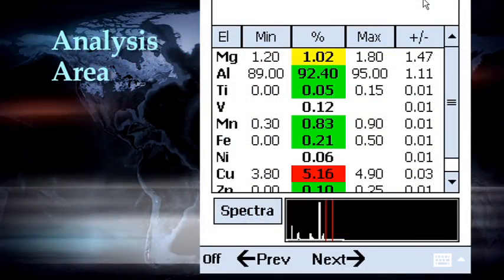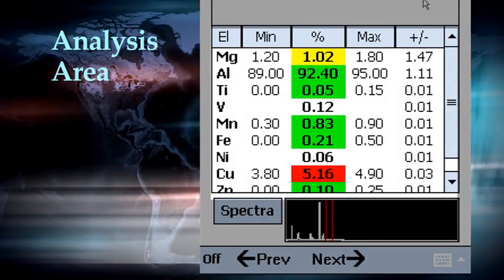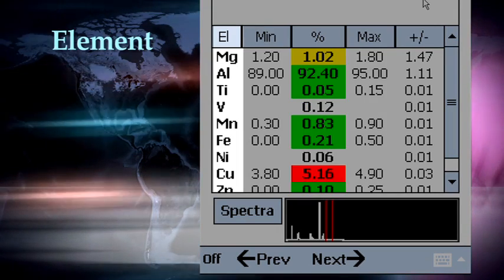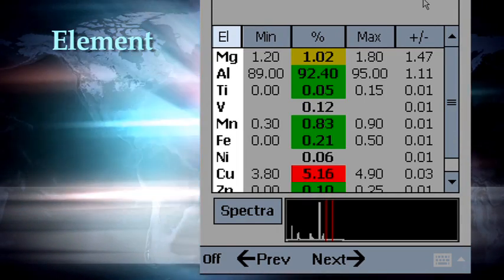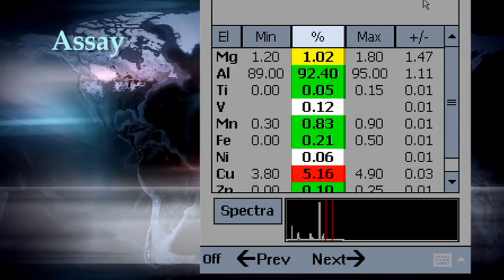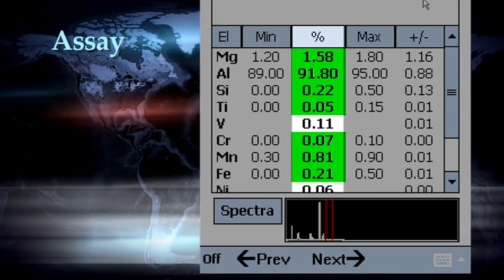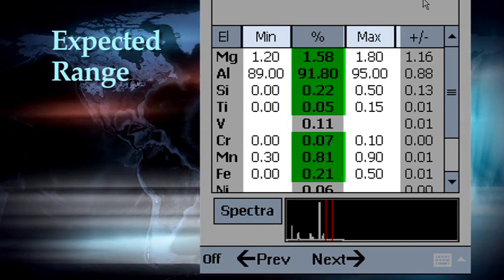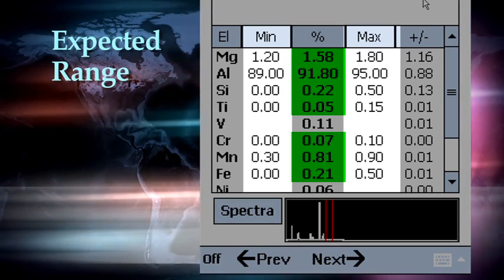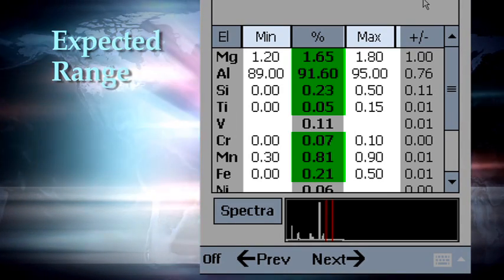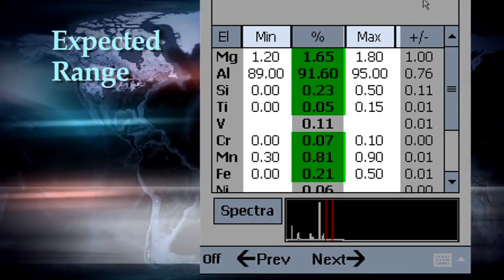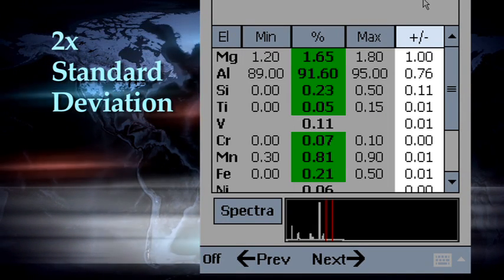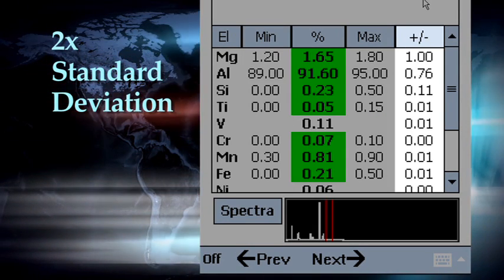In the bottom section of the screen is the analysis of the sample. The first column is the identification of the element. The third column is the assay of the sample. The second and fourth column indicate the expected range of the element in the grade definition displayed. The last column displays 2 times the standard deviation of the measurement.